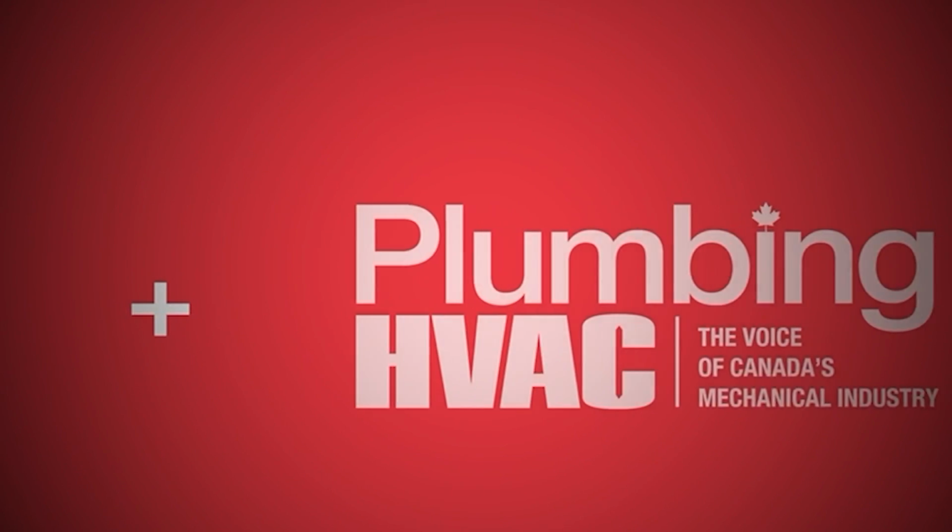Shouldn't be any upgrade then to your electrical or your gas. He's gonna plumb out the hydronic lines, get it all connected, and then fire it up. And by the way, we have one SKU that's capable of handling a variety of different fuels. It's going to be able to handle natural, LP, at altitude, and basically they're going to be able to dial in the combustion via the gas valve. So there's no additional SKUs, no hardware change to accomplish that.